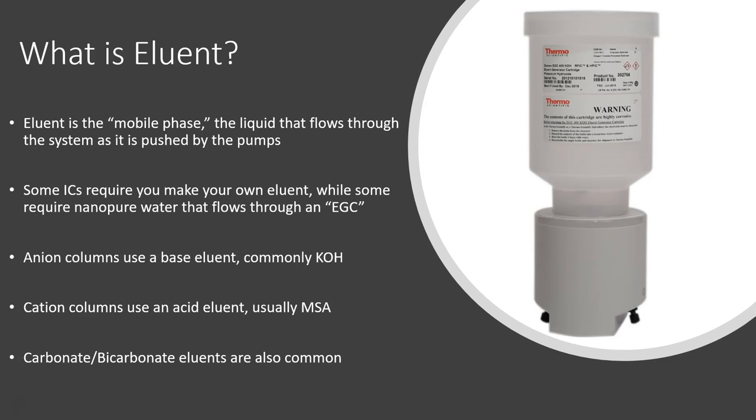EGC means eluent generator cartridge, which uses an electrolytic chamber to turn very concentrated eluent into a more diluted eluent for your IC based on a current that you apply to it. That's what this picture is on the right, this is an EGC.